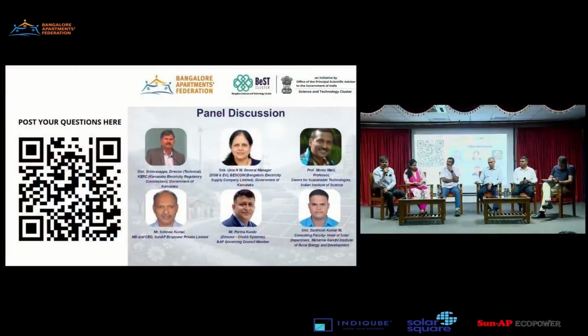Or if you want an individual one. No, space is already there. The existing transformer is already there, replacing that with a higher capacity one. Space is sufficient. CEIG approval is required because once new equipment is added to the transformer, CEIG is the safety keeper as per CEA regulations. So therefore, his safety regulations have to be complied with. Therefore, you need that before commissioning of that.